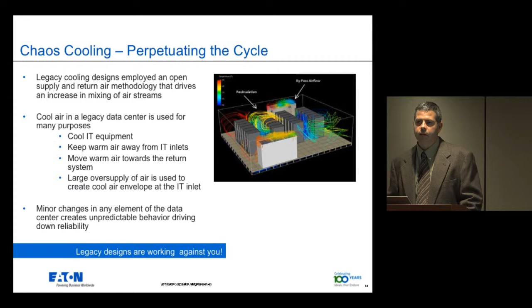So here's a list of the three main types of problems that occur with this chaos cooling. First is recirculation, which is basically when the servers are drinking their own exhaust, right? This will typically happen when the hot air from the back of the rack is coming over the top, typically that's what happens, or if it's at the end of a row, it might come around the side. In either case, there's not enough cold air coming up from the floor. The server fans still need to draw in air, because they're still moving, so they'll take what's available, and that's typically hotter air. It's been pretty well documented over time that the servers at the top of a rack have a higher failure rate than servers at the bottom of the rack, and this recirculation is one of the leading causes.